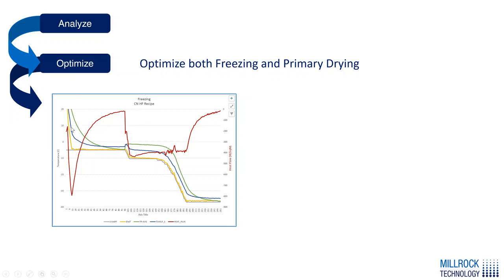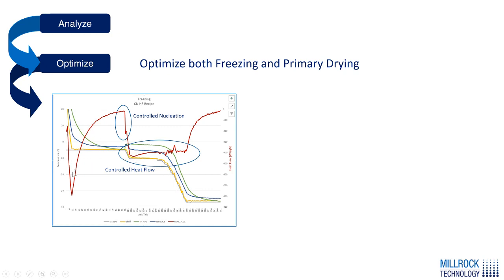Here's an example of the heat flow during a freezing process. This red line is the heat flow, which would be similar to what you would see in a DSC, where the heat flow increases dramatically — in this case in the negative direction because we're freezing — and then comes up and stabilizes out. Once it stabilizes, we know we're done with the super cooling effect. In this case we went to minus five degrees, stabilized, and then performed a controlled nucleation event. We wait for stabilization at minus five, then do our controlled nucleation, getting a dramatic heat flow increase. As the product cools down, we control the heat flow by controlling the shelf temperature, demonstrating the effect during super cooling, controlled nucleation, and then controlling the heat flow post-nucleation.